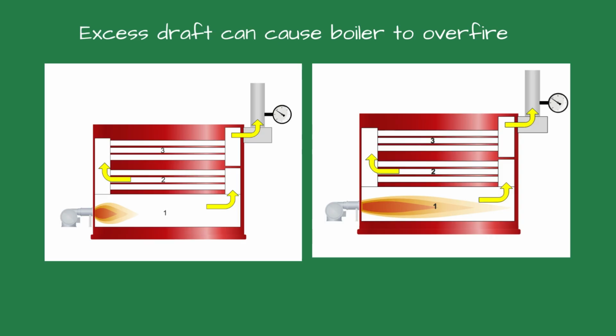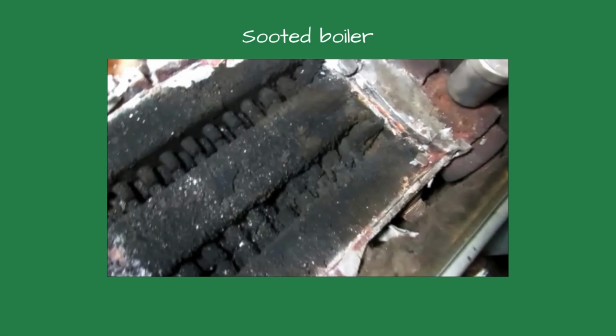Here's why. Steam boilers have a higher stack temperature, which can increase the natural draft beyond the ideal levels. This can lead to faster exit of the combustion gas, reduced heat transfer to the water and steam, and higher fuel bills. Low draft leads to incomplete combustion, which creates soot. That soot insulates the fire side of the boiler. It's like you now have two insulators: scale on the water side and soot on the fire side.